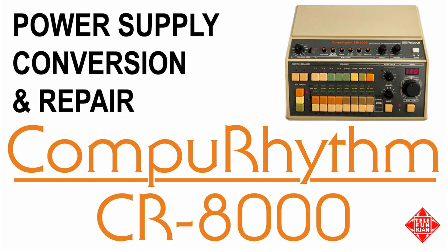To recap, so far we've replaced the faulty power transformer, fixed a broken switch, replaced the power cord and line capacitor, and installed a safety capacitor across the power switch, and replaced all of the old electrolytic capacitors with new ones, upgrading the voltage and temperature ratings slightly to ensure a long life. We've also replaced the fuses in the instrument to those with appropriate ratings for use in North America.